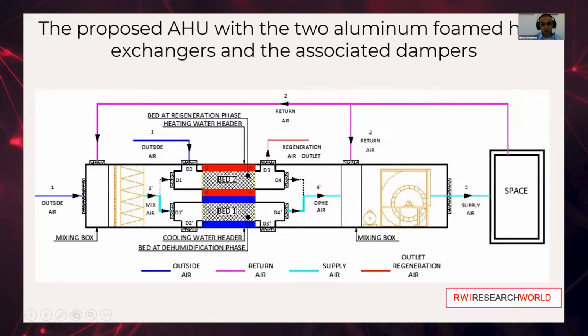Each bed is surrounded from top and bottom sides with water channels to provide cooling or heating water in order to aid adsorption or regeneration. The two-bed configuration was used to allow one bed to perform cooling and dehumidification while the other bed is being regenerated. Outside air at point 1 is mixed with a portion of the return air from the room at point 2 in a ratio that satisfies the fresh air required for the space to provide mixed air at point 3'.